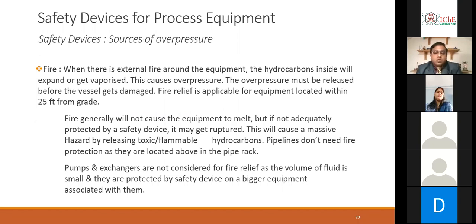Okay, so I have talked about some overpressure scenarios that happen which cause overpressure. So let us see what those scenarios are, what those relief cases are. Generally how we approach in the industry is I have all the cases listed down. A generalized table is there, a checklist kind of thing, and you have to look at each case, look at your system and first tell whether it is applicable to your system or not. Yes or no, that comes first. Then when you say yes, you have to do the calculation. Then your source of overpressure becomes a relief case.